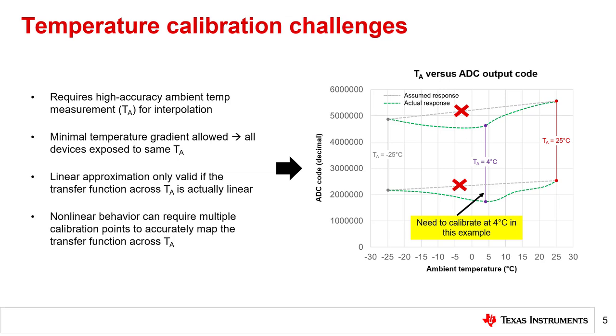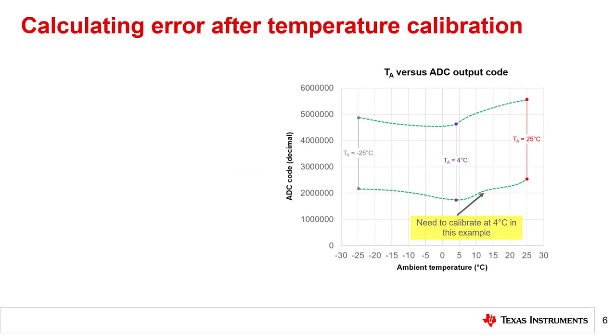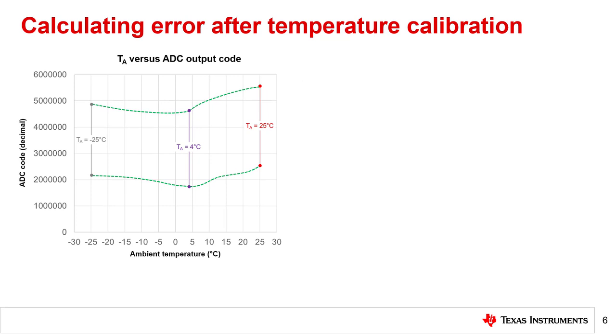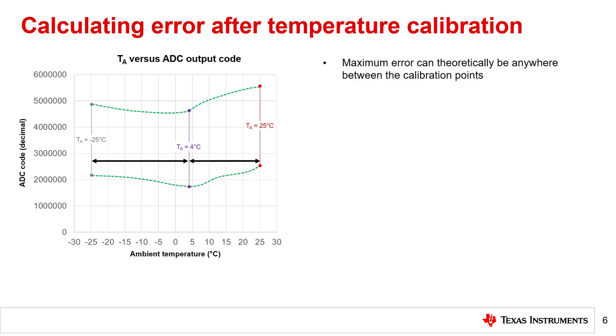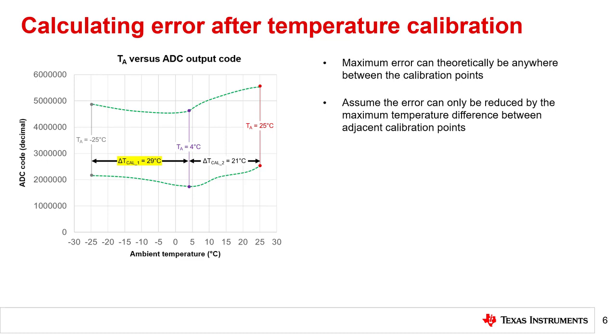Estimating the potential reduction in temperature error by calibration is explored in more detail on the next slide. This plot shows how multiple calibration points can be required for systems with non-linear behavior over temperature. The maximum drift error can theoretically occur anywhere between the calibration points because temperature error is not necessarily linear. Therefore, assume that error can only be reduced by the maximum ambient temperature difference between adjacent calibration points. Assuming this example system is calibrated at negative 25, 4, and 25 degrees Celsius, the maximum ambient temperature difference is delta T cal 1, or 29 degrees Celsius.